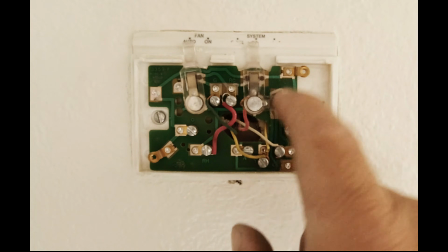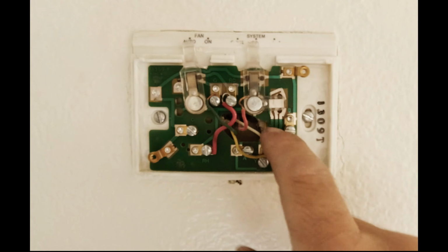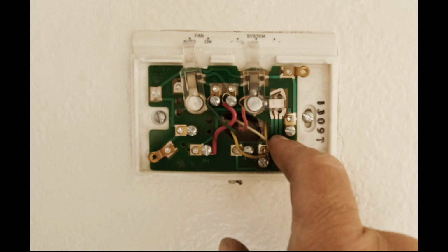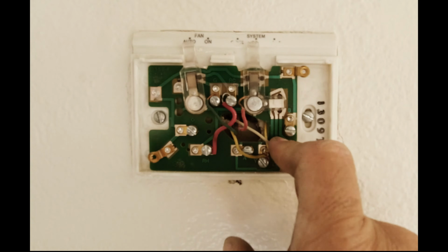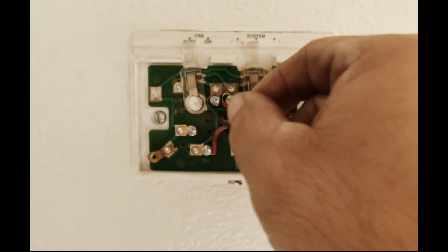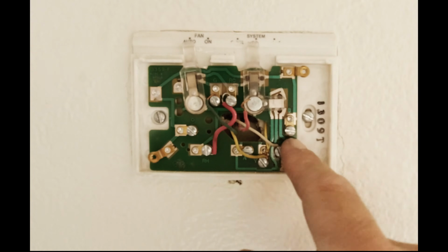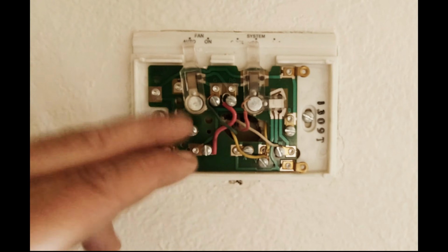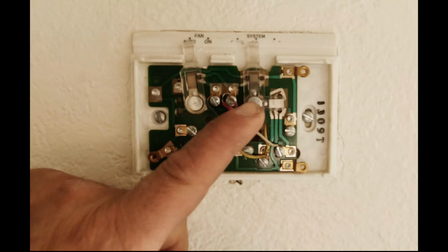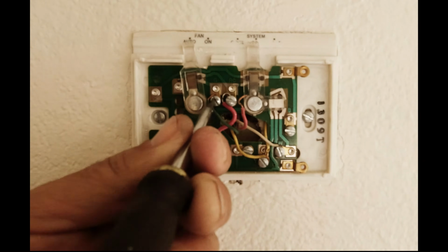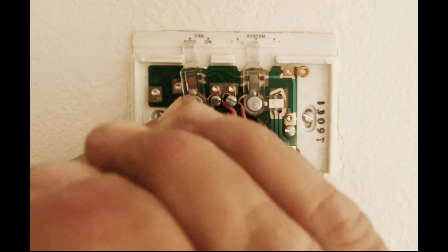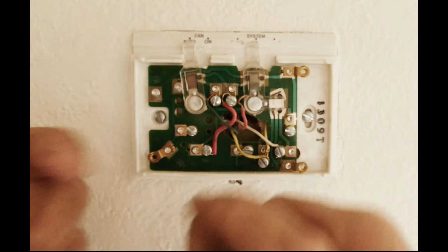and that'll just create another problem, because now you've got to go up to the unit and figure out where that fuse is at and change it. So if you see a C, it's usually a blue wire, or anything connected to a C terminal, make sure the red and the C never touch. The C is really just for digital thermostats where you don't want to use a battery, so they use that C connection, and that avoids you from using a battery.